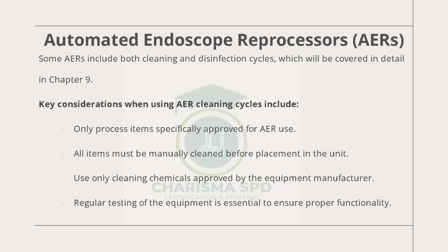Use only approved cleaning chemicals. As I said, some come with already impregnated sponges that we use because they are very delicate and very expensive. All right. Regular testing of the equipment is essential to ensure proper functionality. After cleaning, we test it at the Decon before we wash it. We make sure there are no leakages. If there are, we don't do that. We clean it and then it has to go for repairs. But if there are no leakages, then we completely reprocess it.